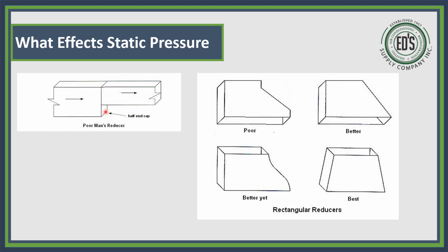This is called a poor man's reducer, where you take a big piece of duct and stick a little piece of duct in and put a piece of metal there, or you do this in duct board. There are no turning vanes, there's no transition. What's going to happen? You're going to have turbulent air right here. So how hard would it have been to come back here and do a line to push this air up and get rid of this whole square? That's called a poor man's reducer, and you will have issues, and that causes static pressure there.